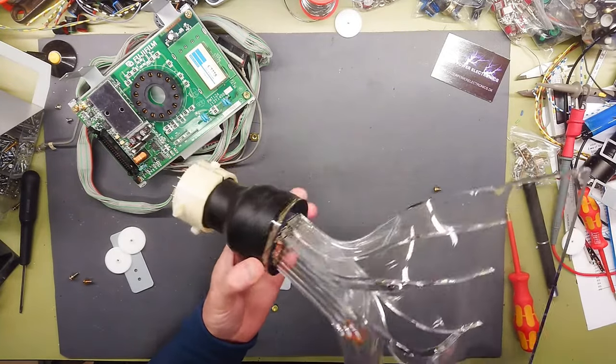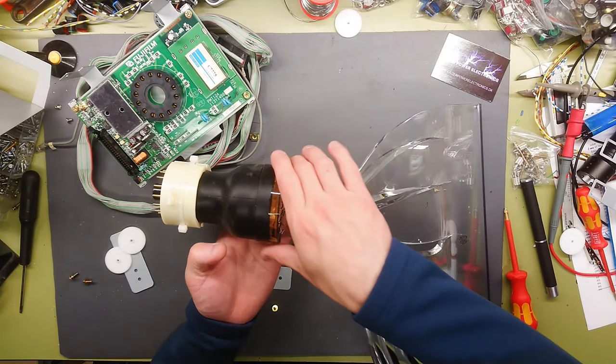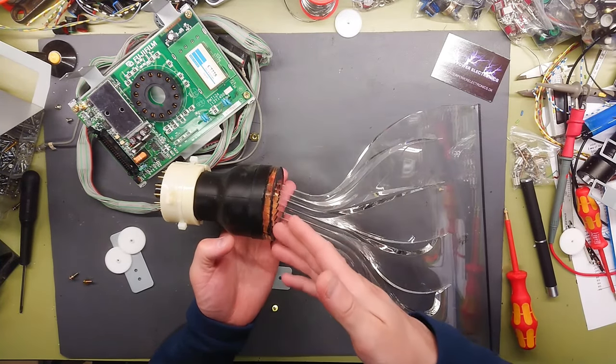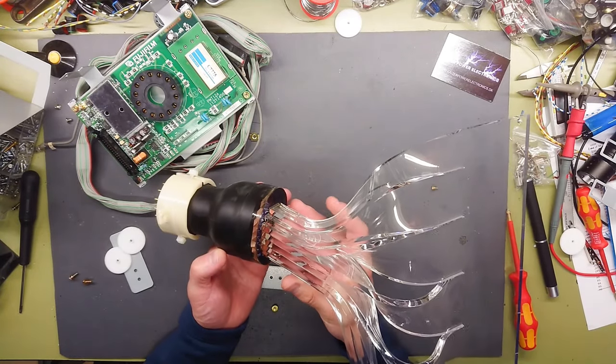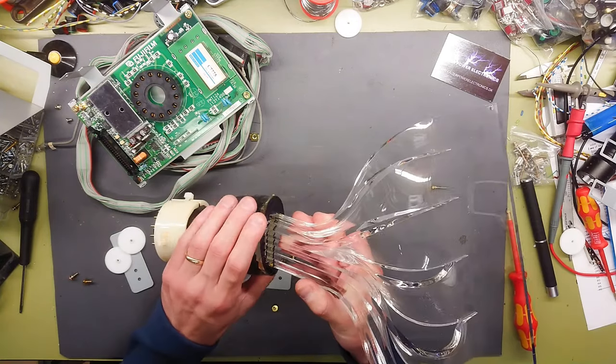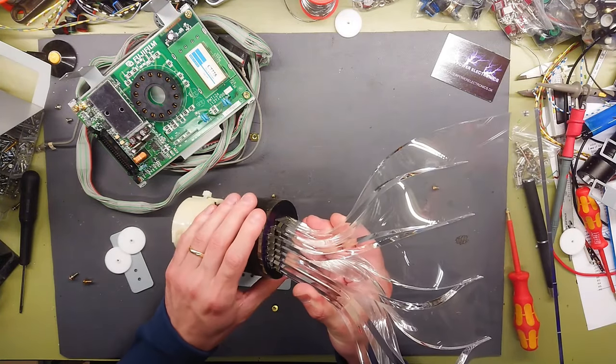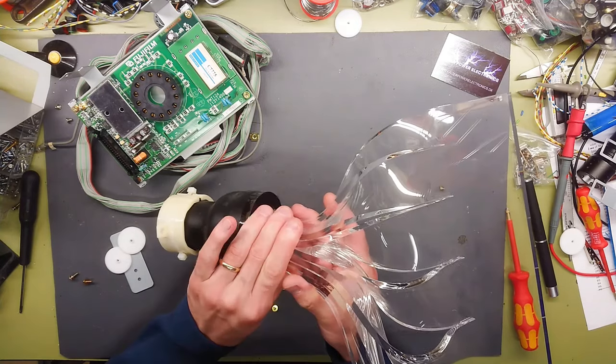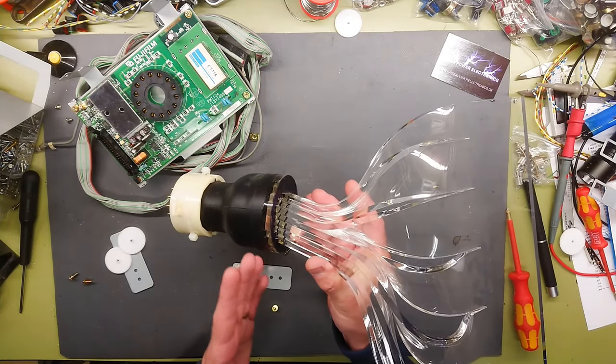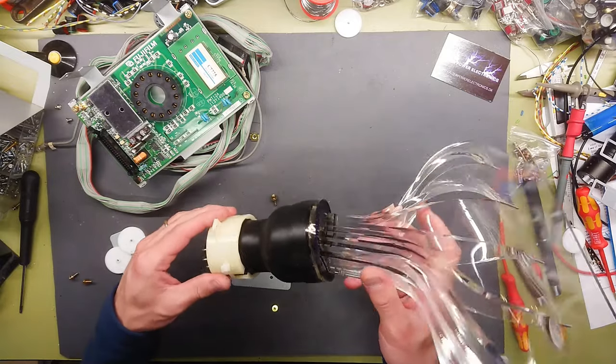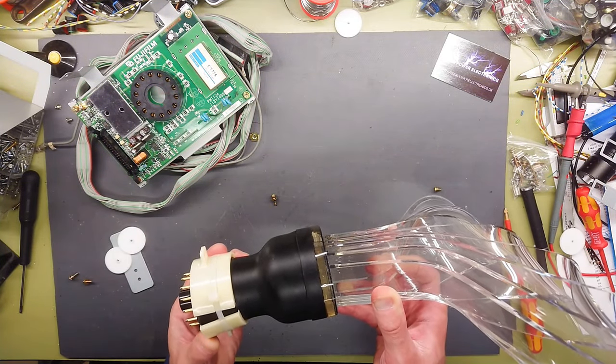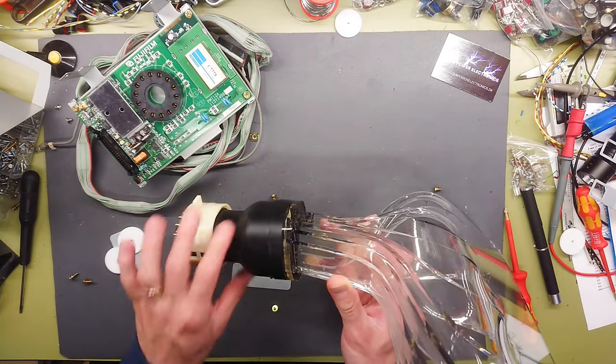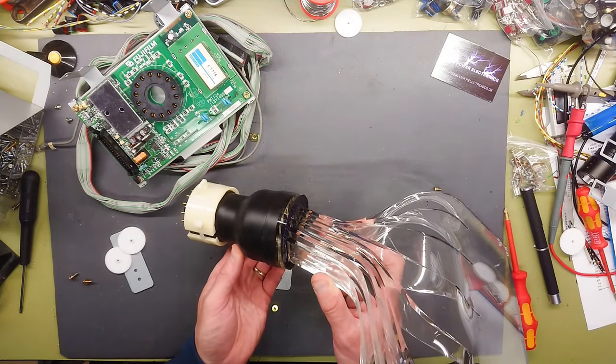It's interesting that this tube sits in a complete rubber gasket. It sits here with silicone, like you have thermal paste, you have optic paste. This silicone material ensures the surface is aligned completely with the tube window. I can pull this off the tube just like some kind of rubber sock.